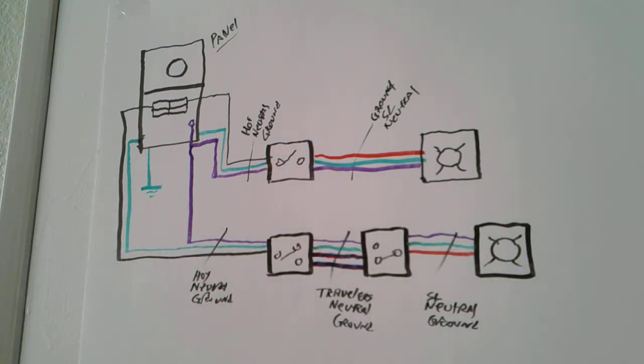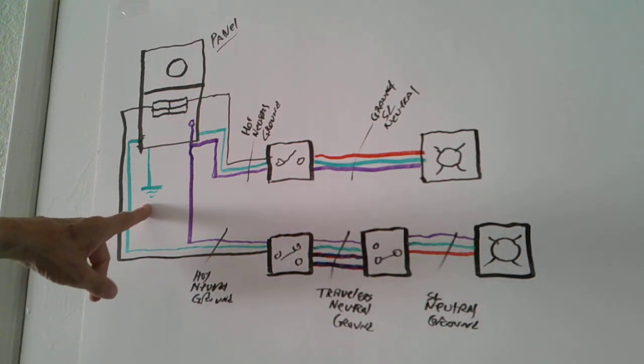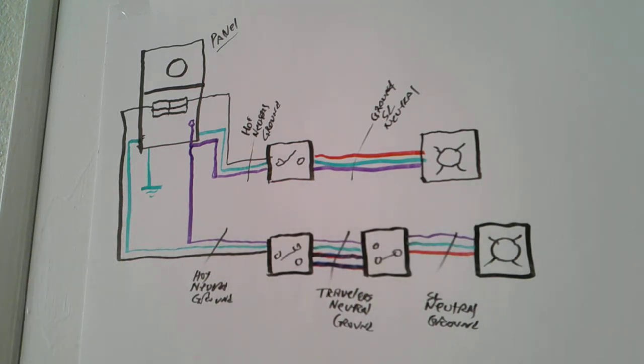Now, in Los Angeles County, I think the code book still says that you have to ground your electrical panel to a gas line. I wouldn't do that personally because gas is explosive. And you really don't want the ground wire to be a conductor unless there's a dead short. So if you have a dead short, it's going to go to the gas line, and you could have a potential problem. But everywhere else we're using ground rods, and we're using building grounds and structural grounds and cold water pipe grounds.